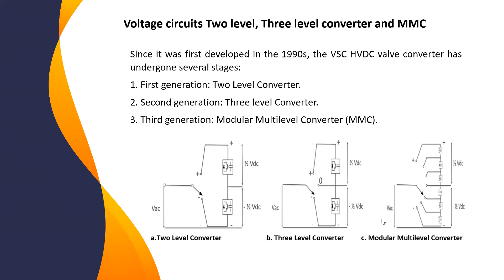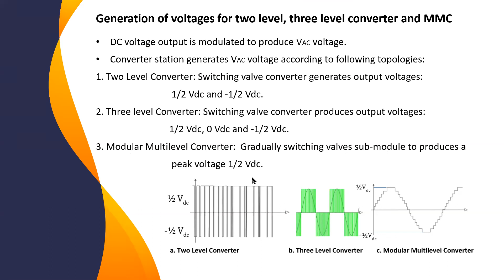This is the configuration of the 2-level converter, 3-level converter, and MMC. So when we are talking about the 2-level converter, actually we build positive, and when we are doing switching of the valve, we produce positive voltage and negative voltage. When we are talking about the 3-level converter, we are switching to three types of voltage: positive voltage, zero, and negative voltage. And then when we are talking about MMC, we are gradually switching the valve submodules. So if we see here, we gradually increase the valve to meet the desired voltage. So we are building the voltage gradually here. But for this, we are only switching 2 times: positive, negative, positive, negative. Here, we switch 3 times: positive, zero, negative, zero, positive. This is the difference between the 3 configurations.